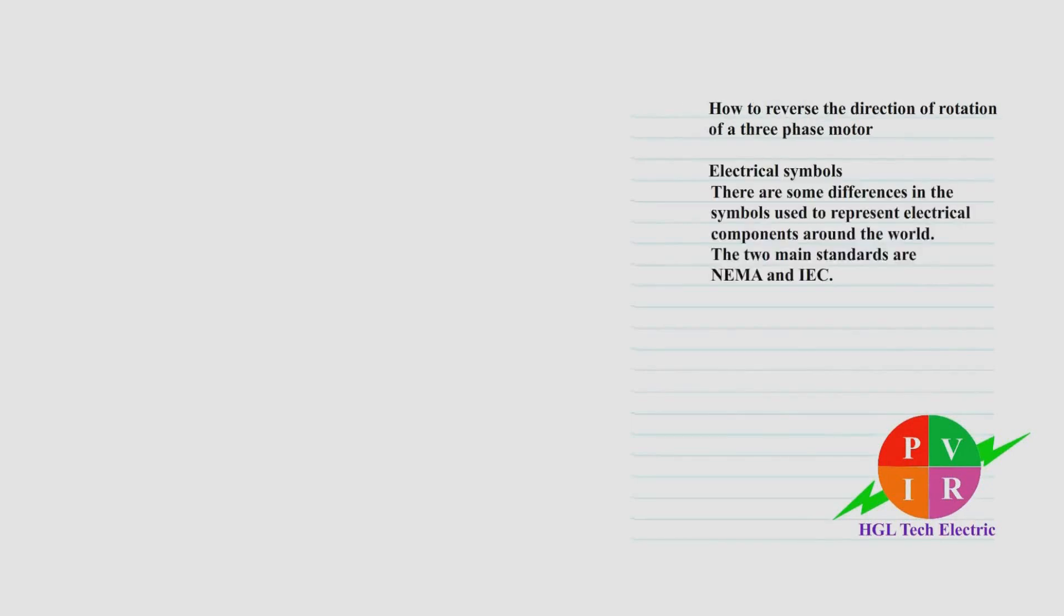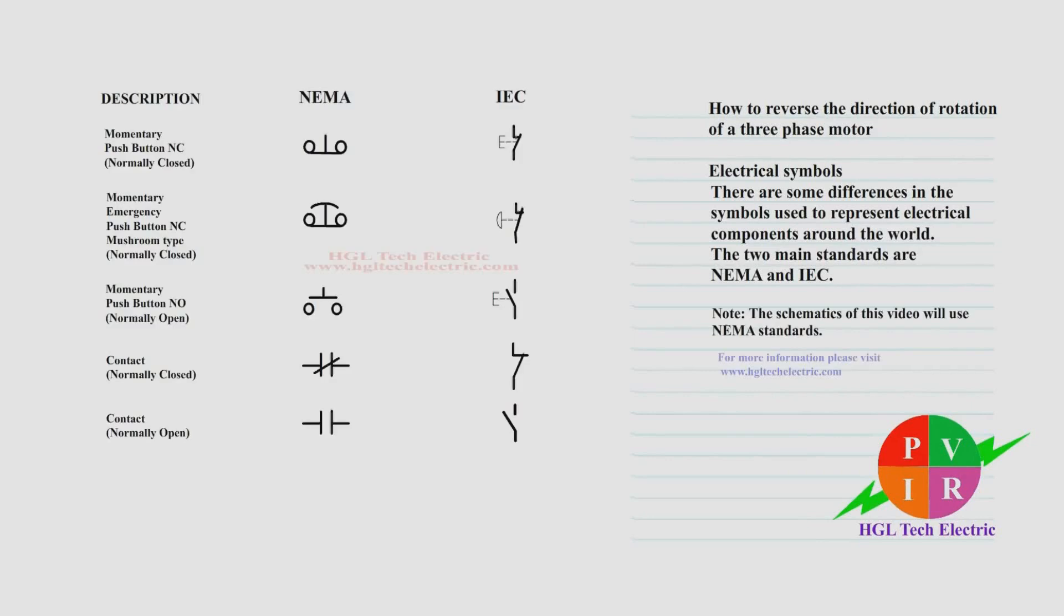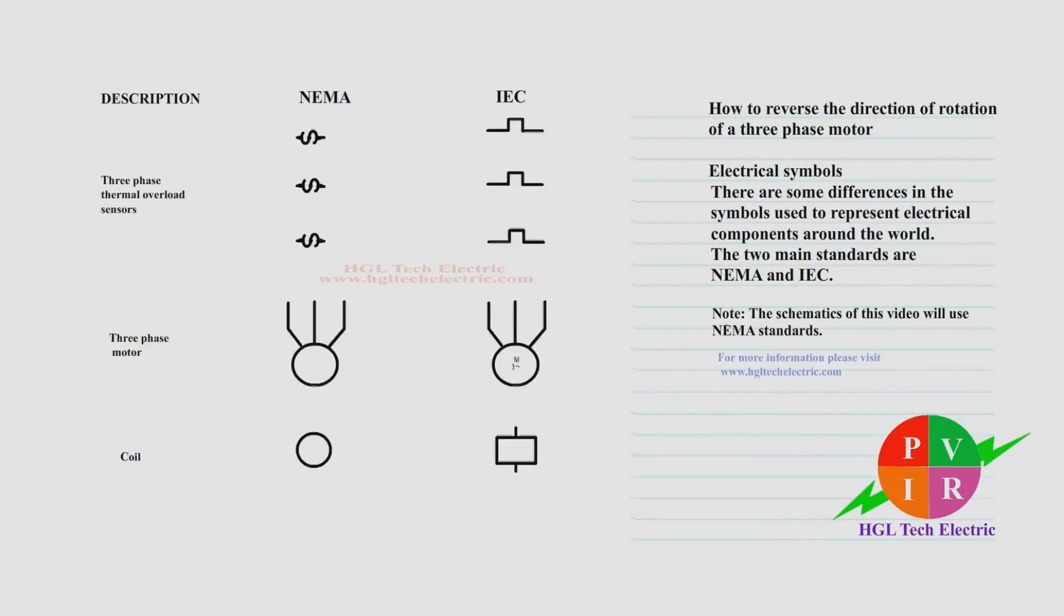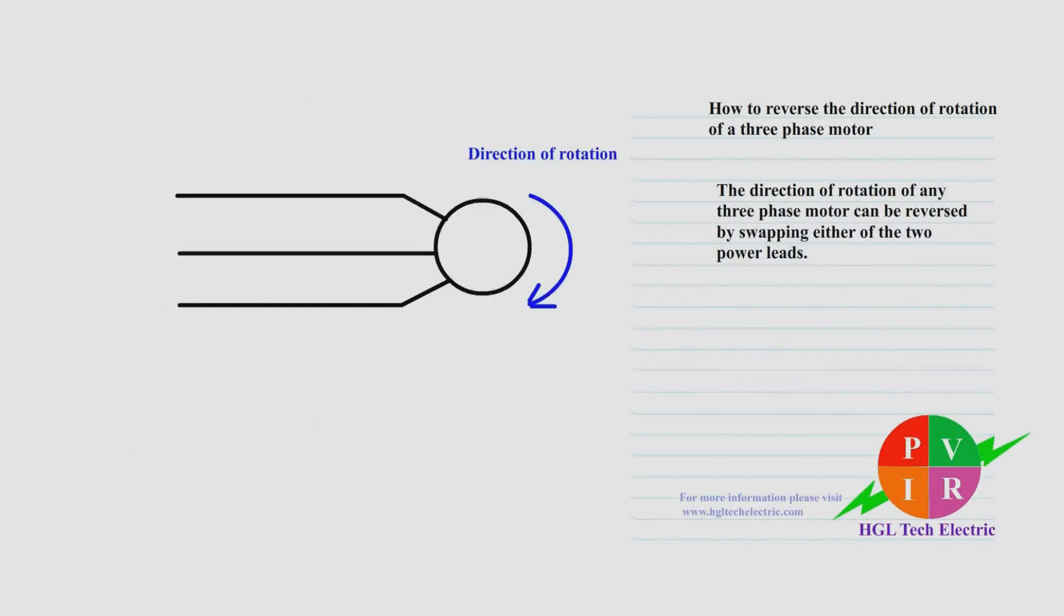There are some differences in the symbols used to represent electrical components around the world. The two main standards are NEMA and IEC. We are going to use NEMA symbols in this video to represent electrical components. The direction of rotation of any three-phase motor can be reversed by swapping any two power leads.